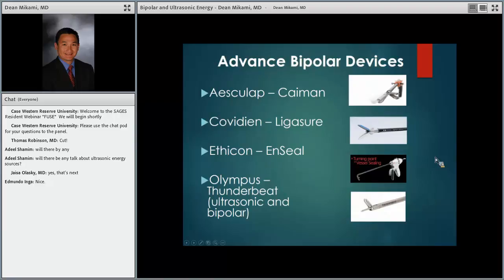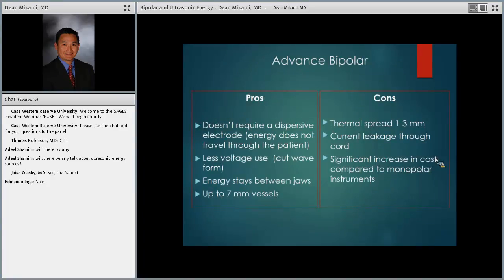Once again, there are multiple different advanced bipolar devices on the market. They all have their different mechanisms that they seal with. But most of the advanced bipolars follow these pros and cons. It doesn't require a dispersive electrode because the energy doesn't travel to the patient. That's good, right? If you have a patient with a pacemaker or AICD, and you really need to use a bipolar or RF energy device versus an ultrasonic device, this is probably a good choice because the energy stays between the jaws and the tissue that you want to treat. It uses a low voltage cut waveform. Energy stays between the jaws, and it can seal up to 7 millimeter vessels.